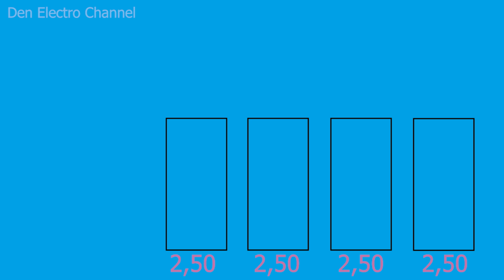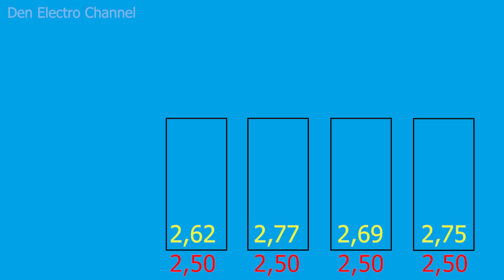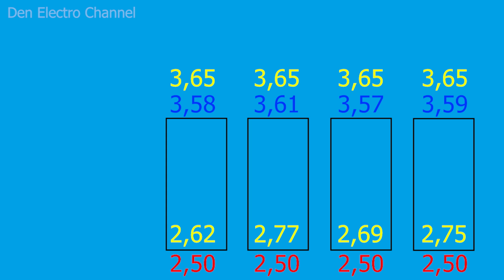After a complete discharge, without load, the voltage may rise slightly—for example, after 2.5 it will become 2.7. And after fully charging, on the contrary, it will fall. After turning off, the voltage may drop to 3.6 or slightly lower. It'll be different for all batteries.